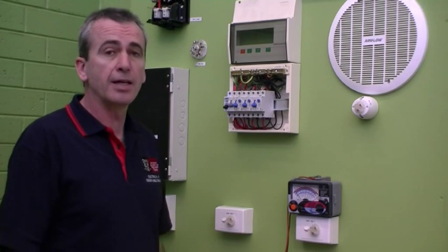I'm about to test the resistance of the earthing system on this installation. I'll start by testing the resistance of the main earthing conductor and of the bonding conductor. When we measure the resistance of an earth wire, we expect a very low value. AS3000 states that for the main earth conductor and the bonding conductor, we're allowed to have a resistance of up to 0.5 of an ohm.